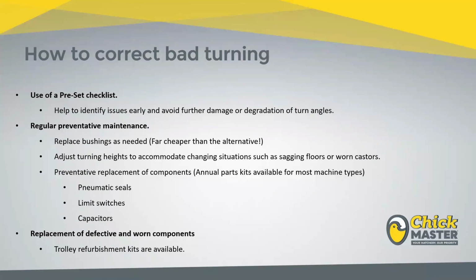However, there's been more and more studies over the last few years that show that preventative maintenance, at absolute worst, is a net gain. So that is to say, if you're replacing a relay or a belt inside a machine, that's not a sunk cost. It's not a cost that you're adding onto the machine. It's a cost that you're just doing a little bit sooner. But your deferred costs, that is your call-outs in the middle of the night, your loss of production, your loss of feasibility, are greatly reduced. So I'd always recommend preventative maintenance in the APK kit. The annual parts kit is a great way to do that. And that's a program that we tailor for pretty much every customer.